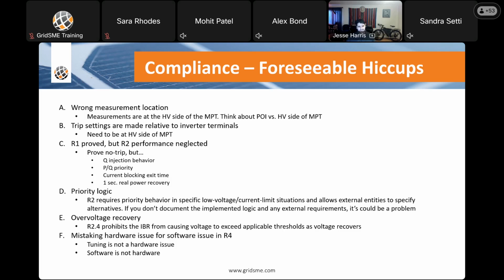Priority logic: R2 requires priority behavior in specific situations and allows external entities to specify alternatives, but you need to document the implemented logic and any external requirements. If you don't, you risk being non-compliant. Overvoltage recovery: remember requirement 2.4 prohibits the IBR from causing voltage to exceed applicable thresholds. So again, just make sure in your models that these are sufficient.